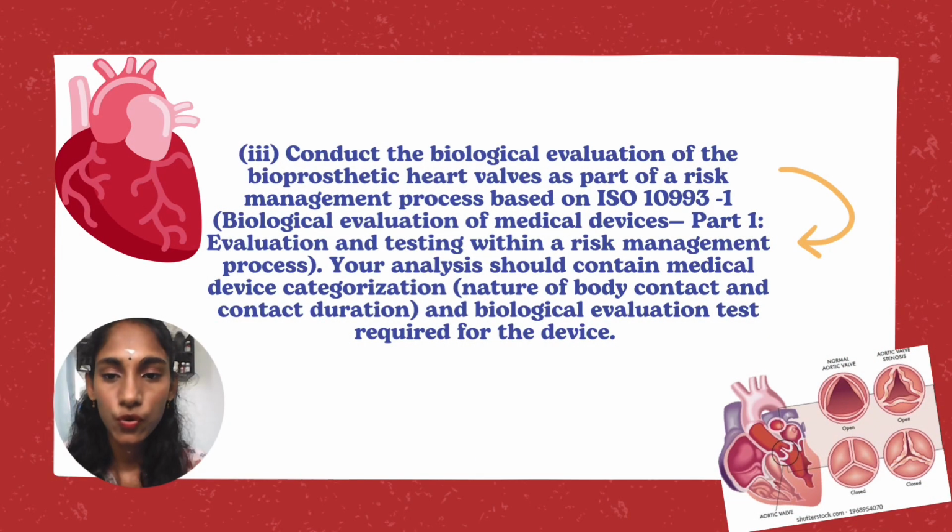Next, I would like to go to question 3, which is to conduct the biological evaluation of the bioprosthetic heart valve as part of a risk management process based on ISO 10993, Biological evaluation of medical devices, Part 1: Evaluation and testing within a risk management process. Your analysis should contain medical device categorization, nature of body contact and contact duration, and biological evaluation tests required for the device.